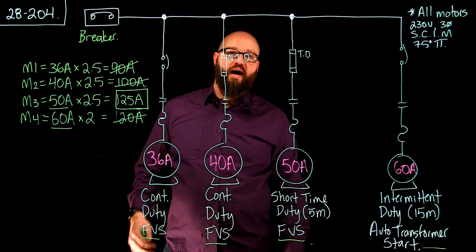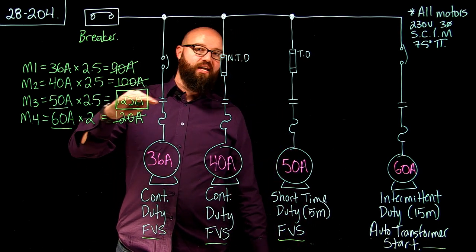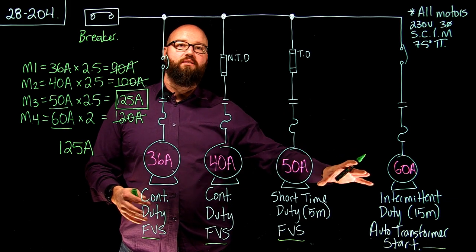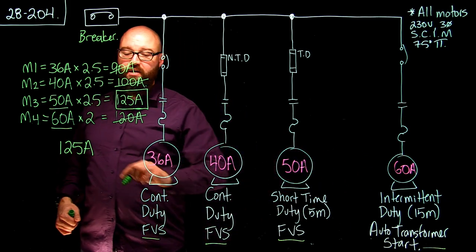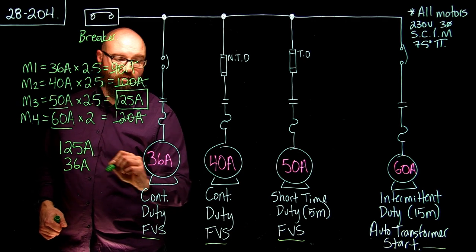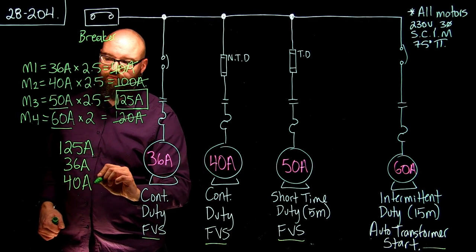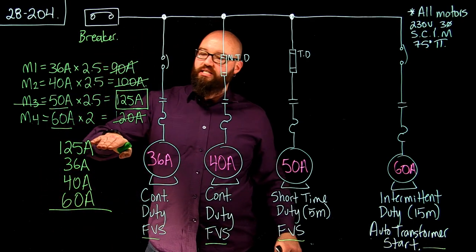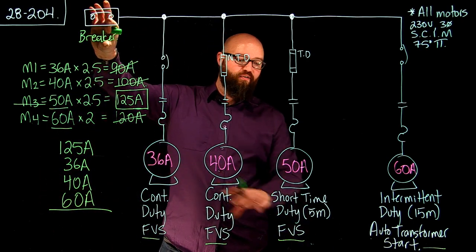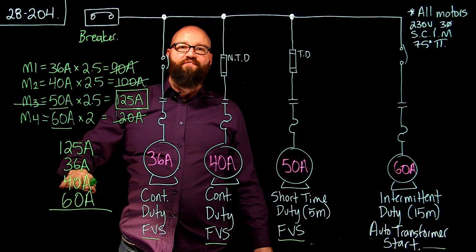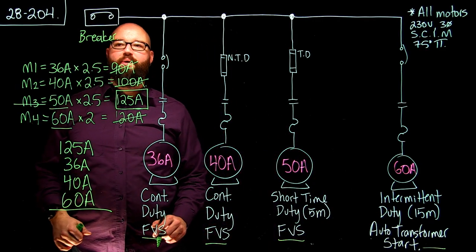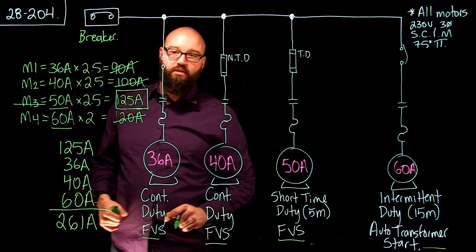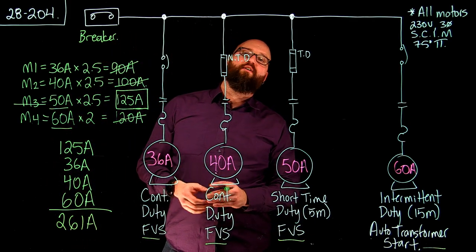Once we know which motor has the highest calculated value, we take that calculated value — in this case, 125 amps — and we add the rest of our FLAs (not the calculated values, just the FLAs). So we go: 125 plus 36 amps, plus 40 amps, plus 60 amps. That is the highest calculated value with the breaker in mind, plus the FLA of all the remaining motors. We end up at a maximum calculated setting value of 261 amps.